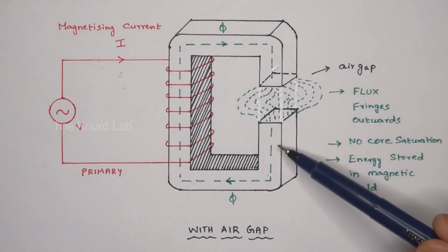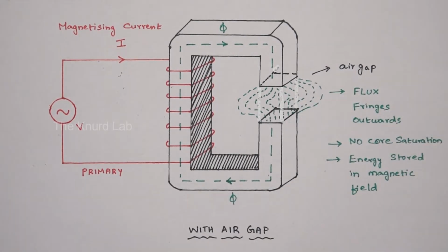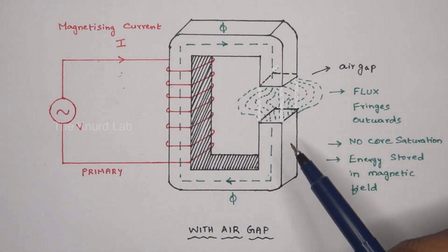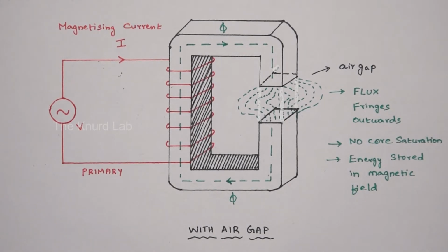The flux lines start to fringe outwards, causing a non-uniform flux density in the core, before passing through the core again and completing the magnetic circuit. If you recall the water through the pipe analogy, you can understand that because of this, the core is no longer saturated, and you need extra current to maintain the flux density.